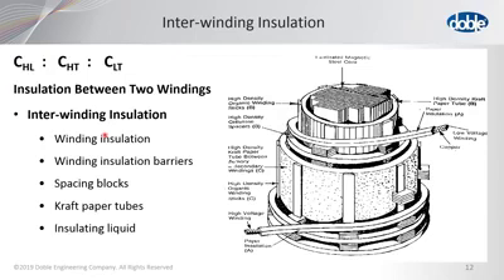So in other words, a leak in the transformer is not a reason not to do the test. Test can definitely be performed. Now, if you really feel that the transformer is wet, let's say you've already done some oil quality tests and you know it's wet, you might want to dry it out even before you do the test.